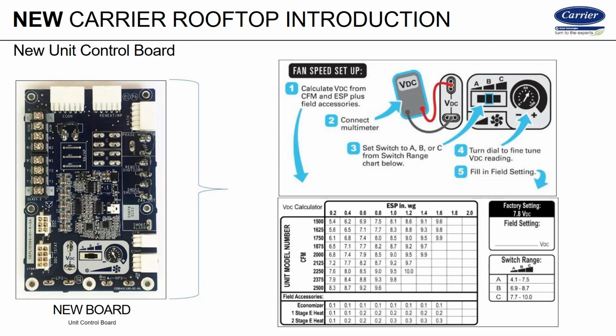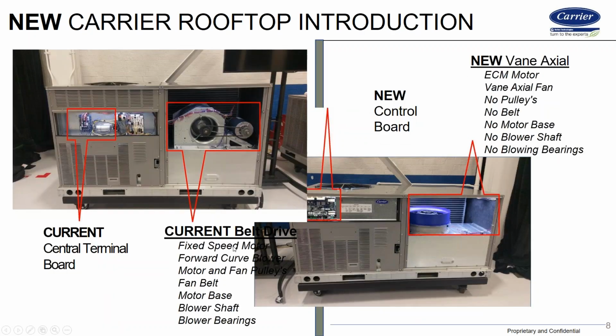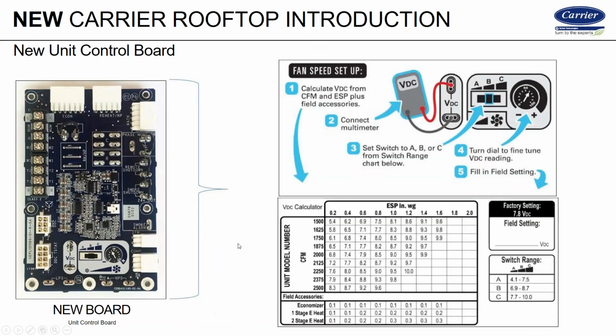You should take the time again to measure external static pressure and know what your desired CFM is. Any questions there? We're going to move on from the dip switch settings from here. We do have one question. Trinidad writes, how can we tell if the unit is low or high static?